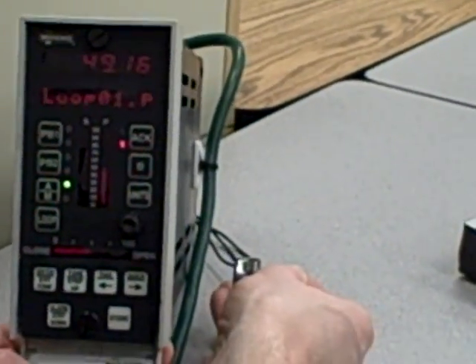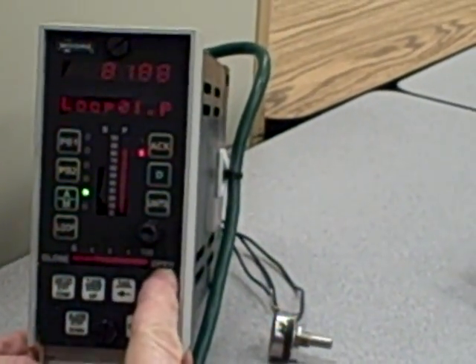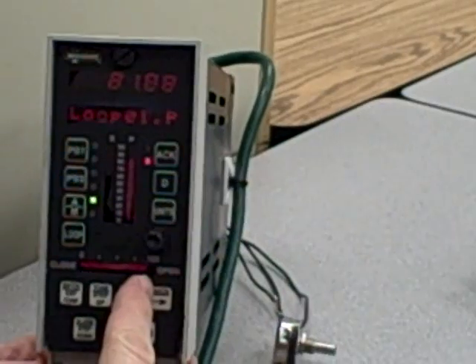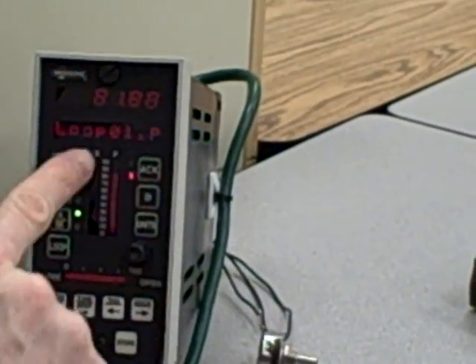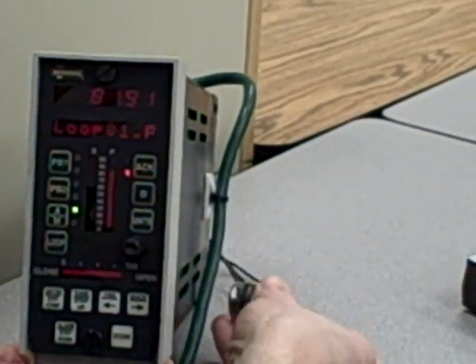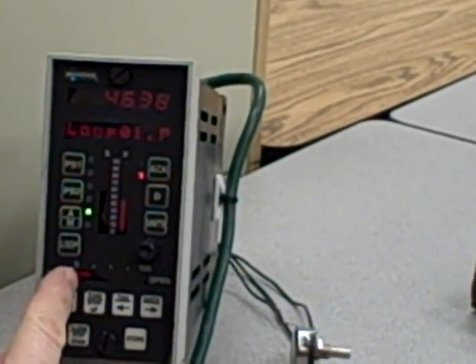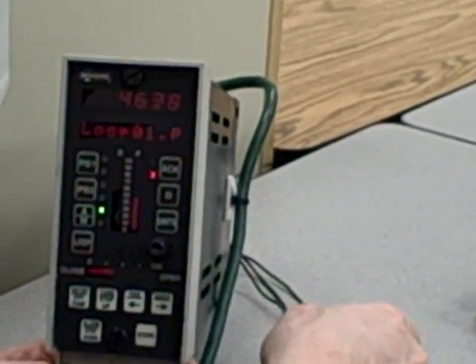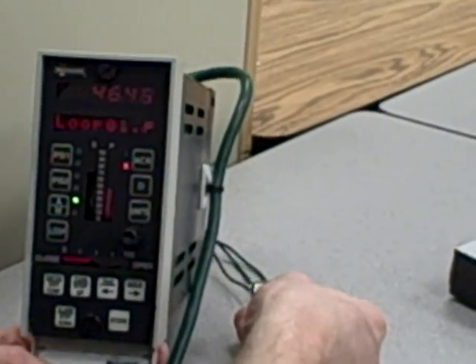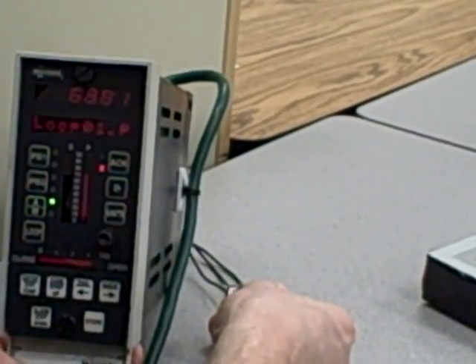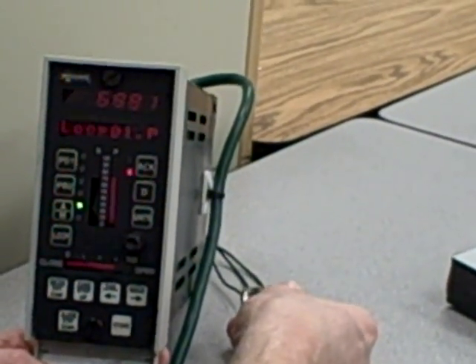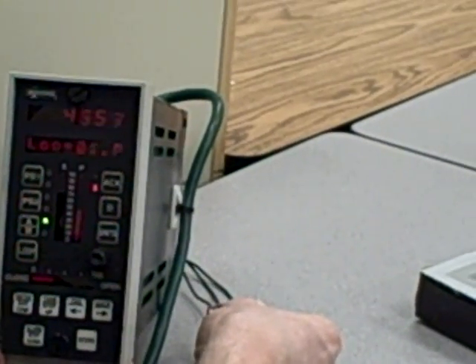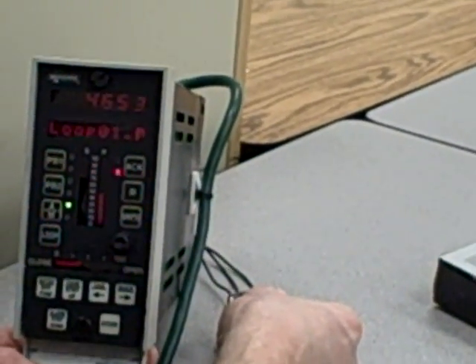So watch as I increase the process variable. It spikes up, and then it settles into its new value. Now I'll decrease the process variable. It spikes down, and then it comes and settles up. So again, every time I move my process input, I get a spike on the output, and then it settles. Every time I move the process input, I get a spike on the output, and then it settles. That is a lead function.